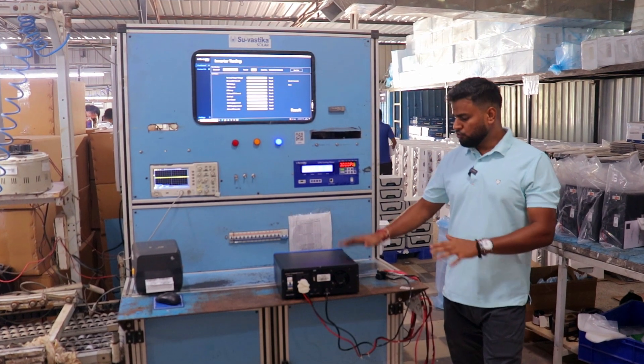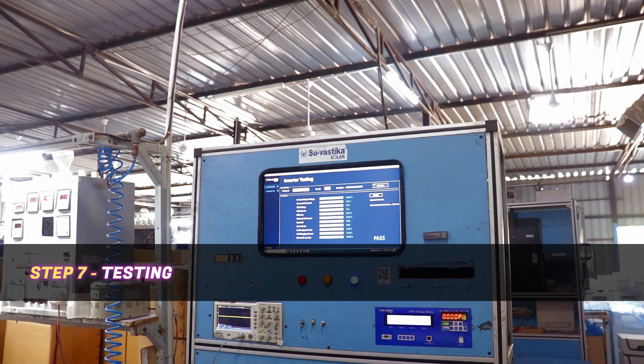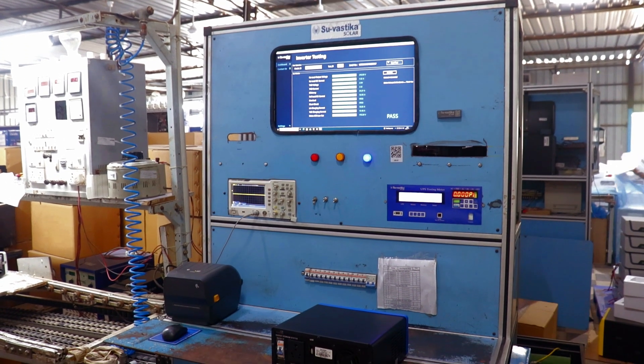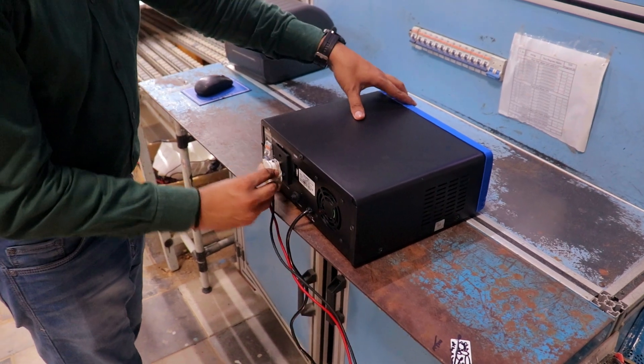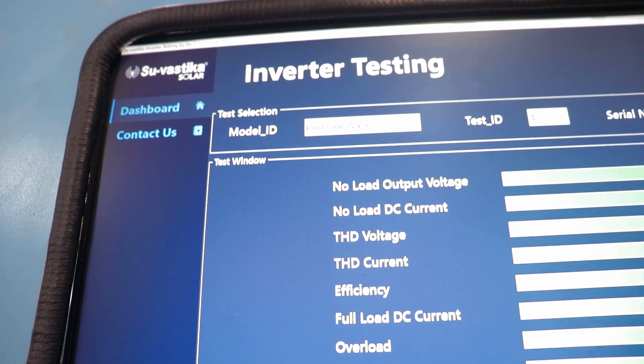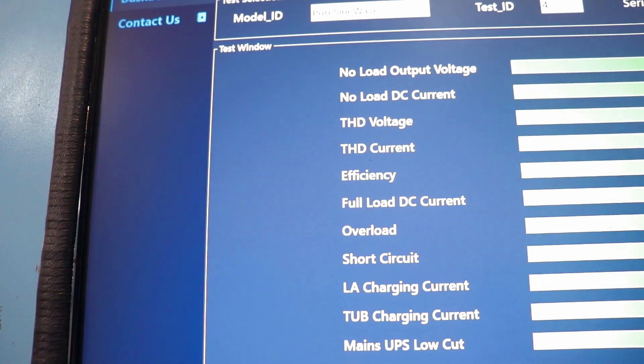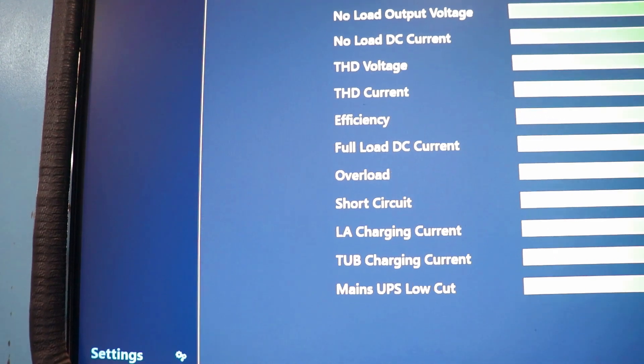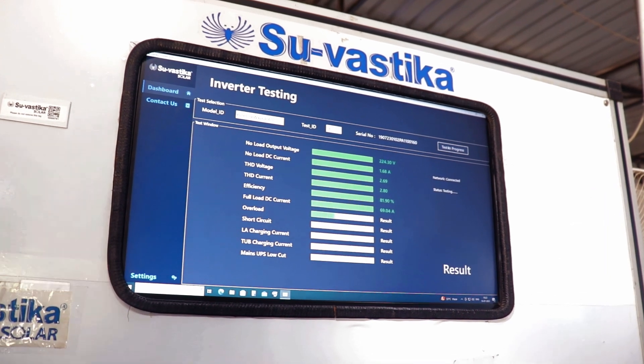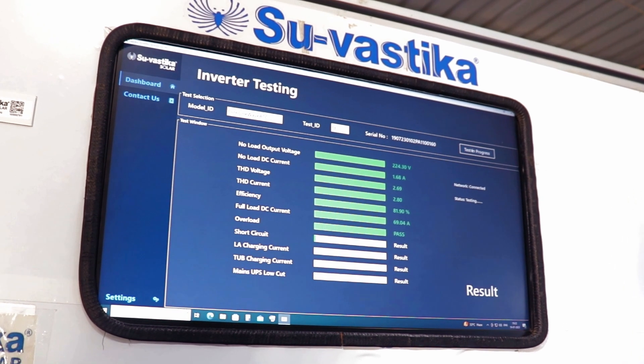Once our model is ready, before we pack it, we test it to check if it is working properly. There is an automatic testing machine — the model and parameters are already selected. You connect this model with the machine, select the model, and start the test. The tests include: voltage test, current test, THD test, efficiency, full load DC current, overload protection, short circuit protection, and voltage test. When all tests run, each part turns green, and finally you get the output result — whether this system is passed or failed.